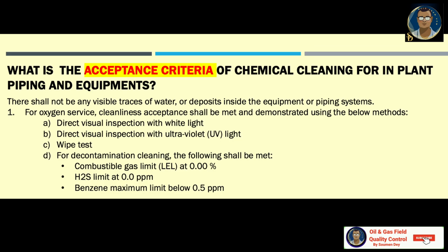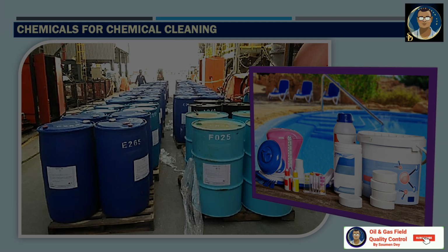For oxygen service, cleanliness acceptance shall be met and demonstrated using methods like direct visual inspection with white light, direct visual inspection with ultraviolet light, and wipe test. For decontamination cleaning, the following conditions should be met: combustible gas limit LEL at 0.00%, H2S limit also 0.0 ppm, and benzene maximum limit below 0.5 ppm.